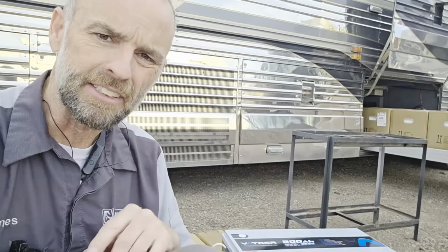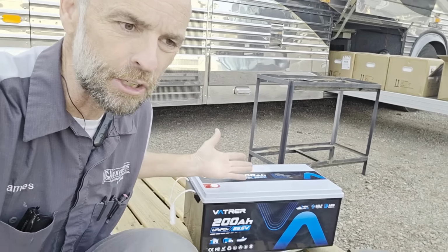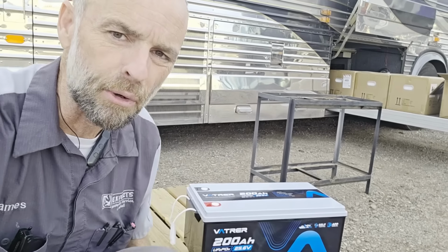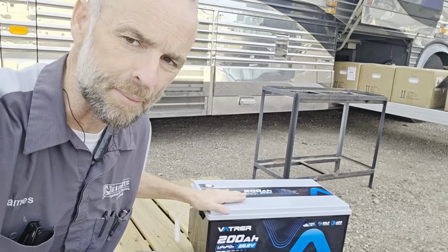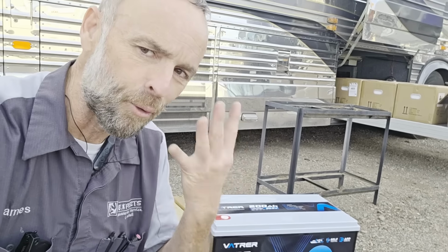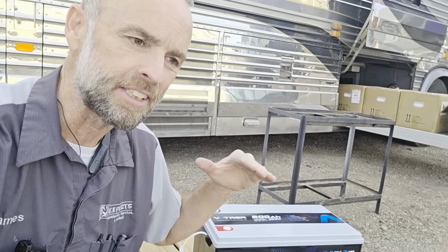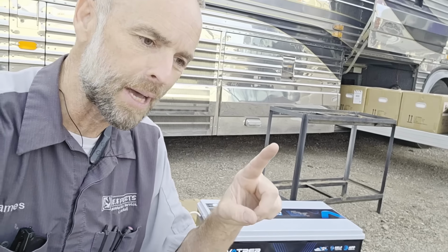It also has built-in redundancy, so if one battery went bad, I'd still have 3 good 24 volt batteries and could just remove the bad one from the system. Whereas if I have 4 12 volt batteries wired in series and parallel, losing one battery basically leaves me down to 2 batteries, but it's really just one 24 volt battery. I know it doesn't make a lot of sense, but let me show you something.